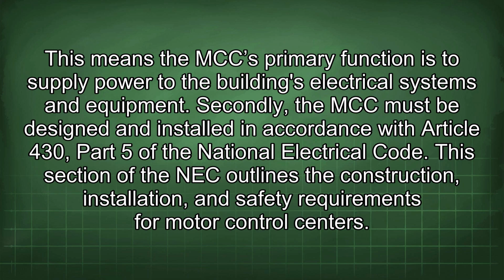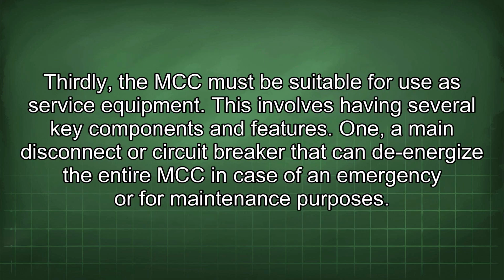Secondly, the MCC must be designed and installed in accordance with Article 430 Part 5 of the National Electrical Code. This section of the NEC outlines the construction, installation, and safety requirements for motor control centers. Thirdly, the MCC must be suitable for use as service equipment. This involves having several key components and features.